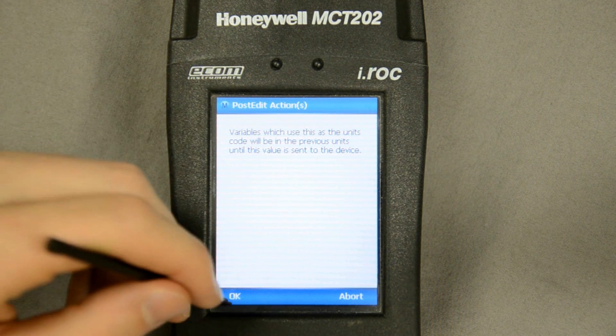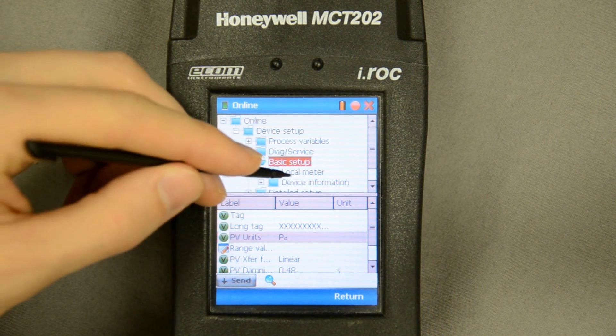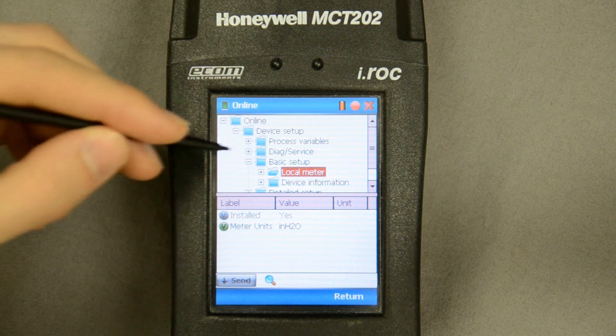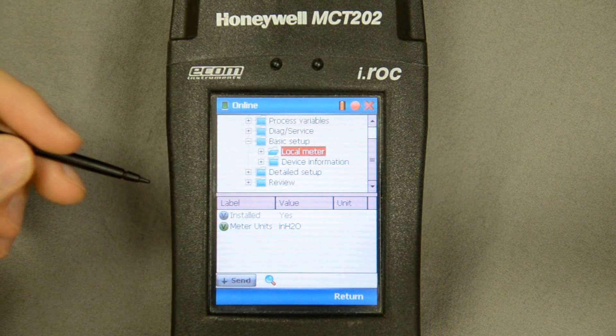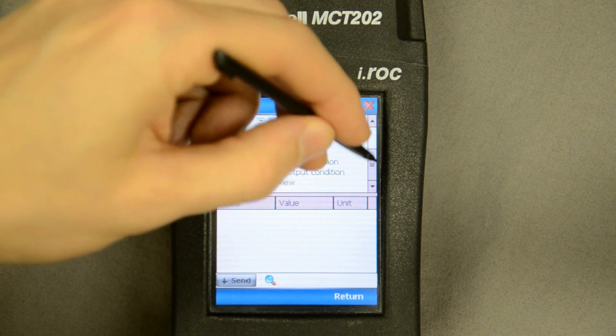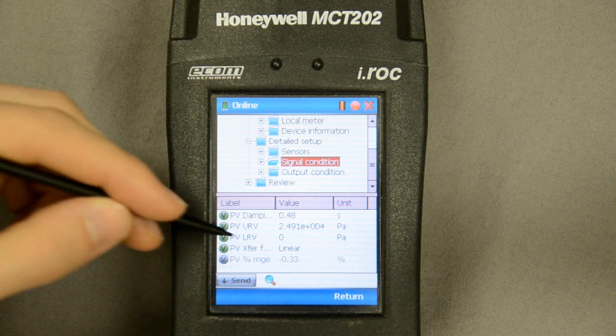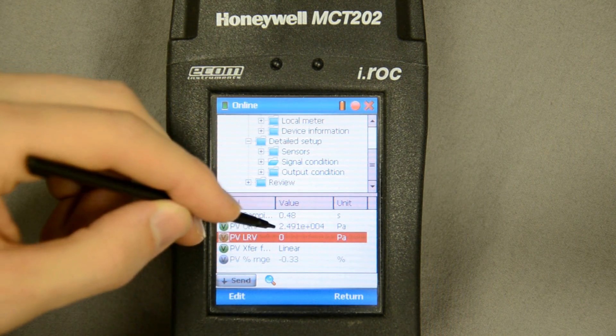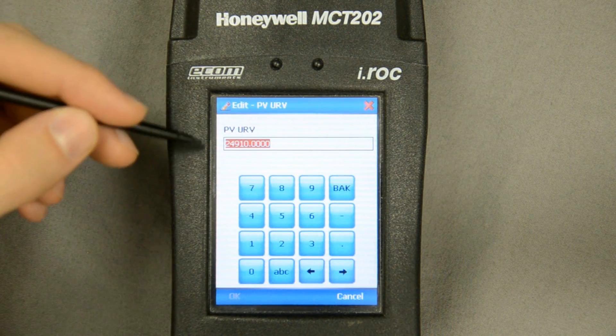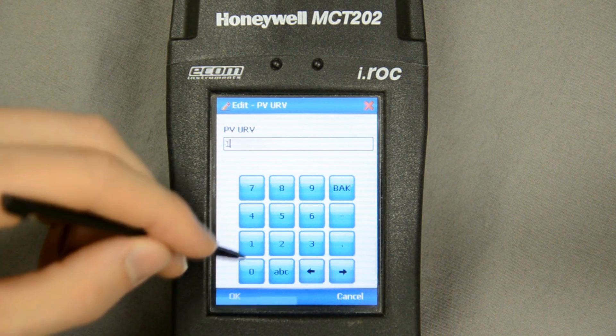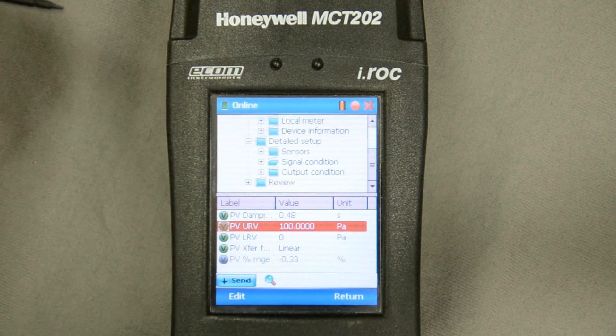It's going to force me to confirm that change. Now in the basic setup I have an interface to the local meter — if I want to change the displayed inches of water column I can go in and change it just like I did the sensor. In the detail setup I can change more parameters. The lower range value is currently set to zero; I can change the upper range value. I'll plow through the warning again and change it to 100 inches.